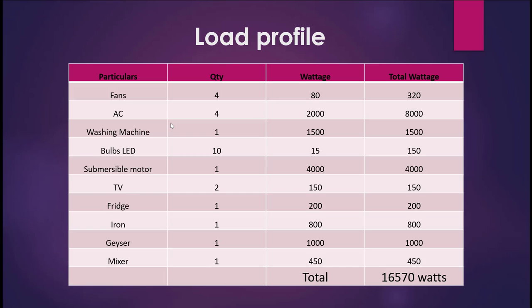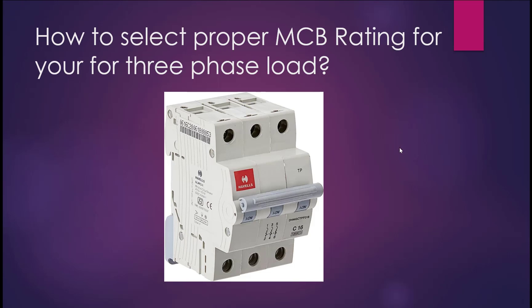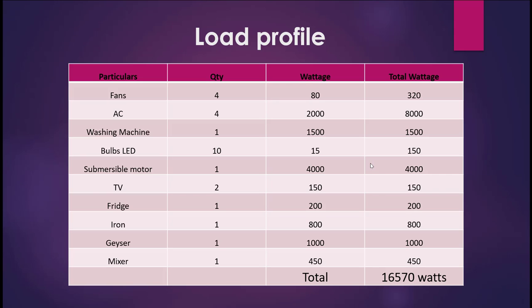For example, take a load profile: you have fans, AC, washing machine, bulbs, and a submersible motor, TV, fridge, iron, geyser, mixer, etc. Each equipment has a wattage value. AC is taking 2000 watts, fans 80 watts, bulbs 15 watts, and the submersible pump is around 5 HP — which when converted to kilowatts is approximately 3.73, so for calculation purposes I took 4 kilowatts. The total wattage comes to 16,570 watts.